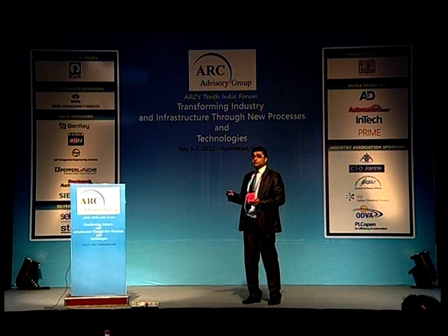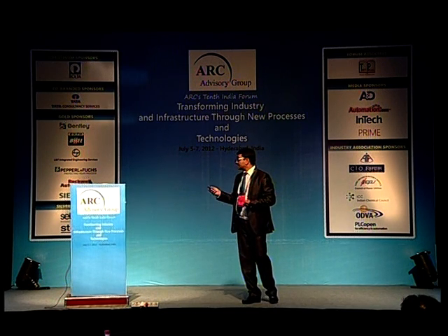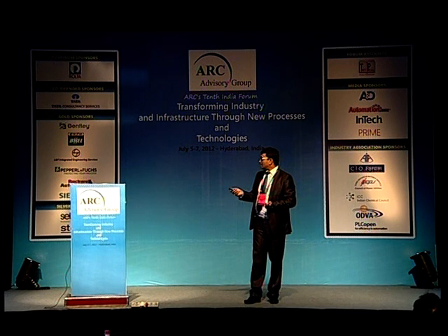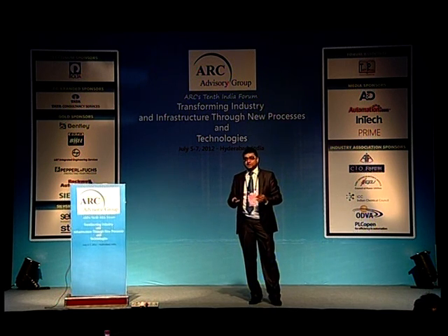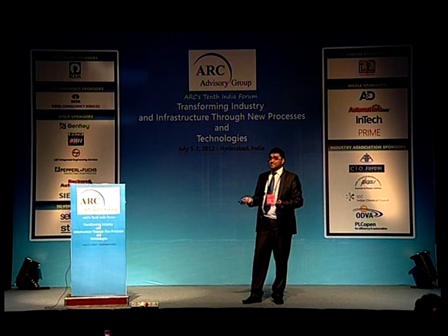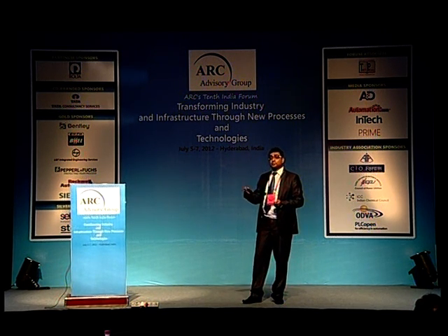SR1 is also another module which gives you lifetime consumption of the thick wall components like the drum, superheater headers, and reheater headers. It is basically a TRD based system which calculates the lifetime consumption based on fatigue and creep, because in the initial period of a power plant, before going into final commercial operations, it goes through a lot of startups and shutdowns. All those instances are captured, the data is captured, and it calculates the life consumed on a continuous basis.